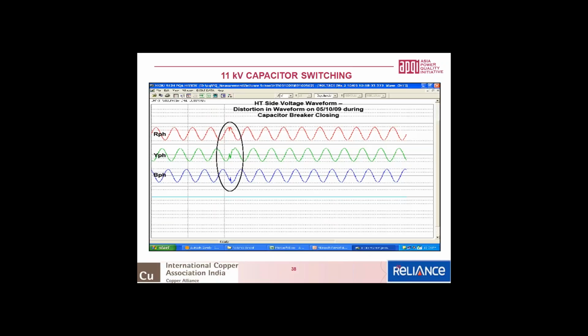Whenever you are using an 11 kV, 33 kV or 6.6 kV capacitor, whenever you switch, you will see some notches in the voltages. The connected equipment should be able to withstand these notches repeatedly. In addition, capacitor switching is one of the most onerous duties for breakers. Many breakers have failed on capacitor duty, which is one of the reasons why, when ordering breakers for capacitor duty, you have to be extra careful.